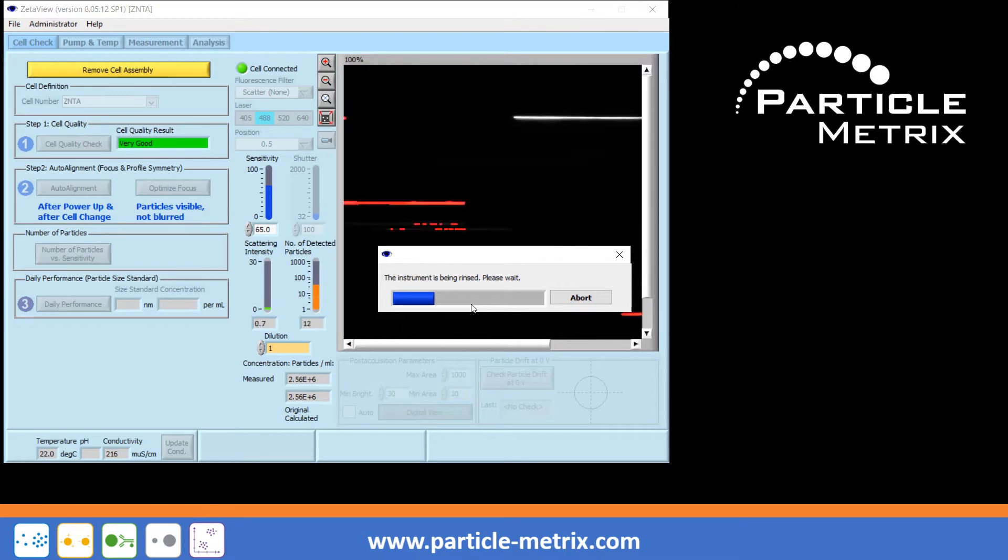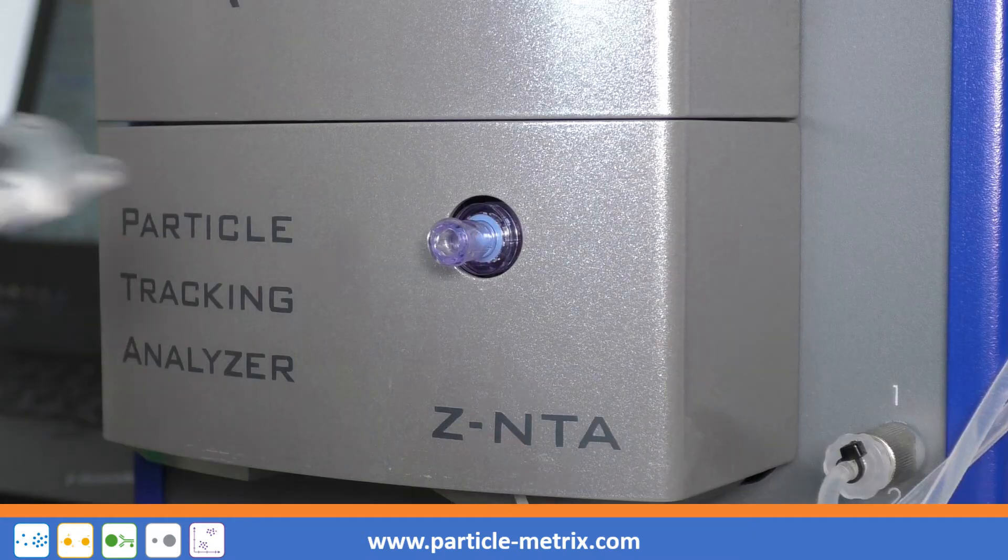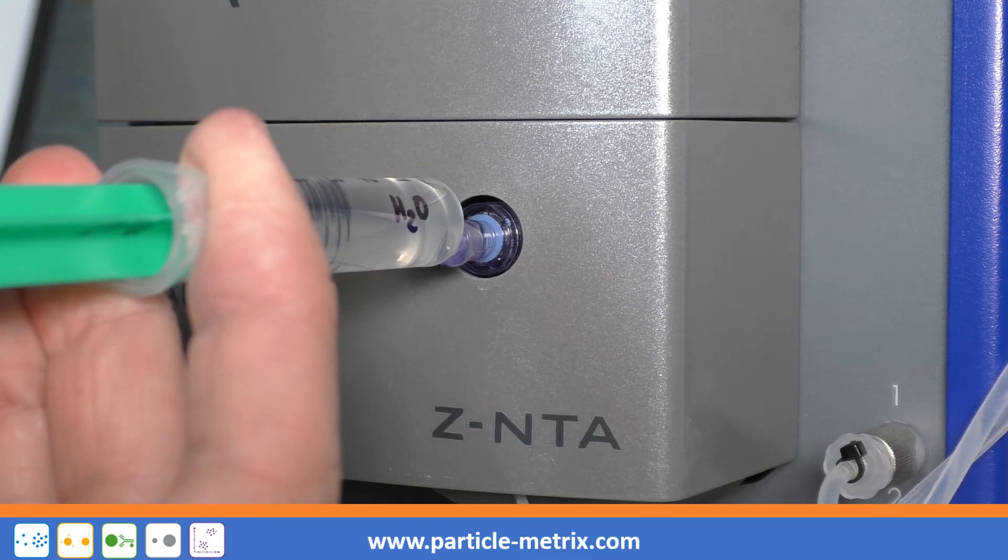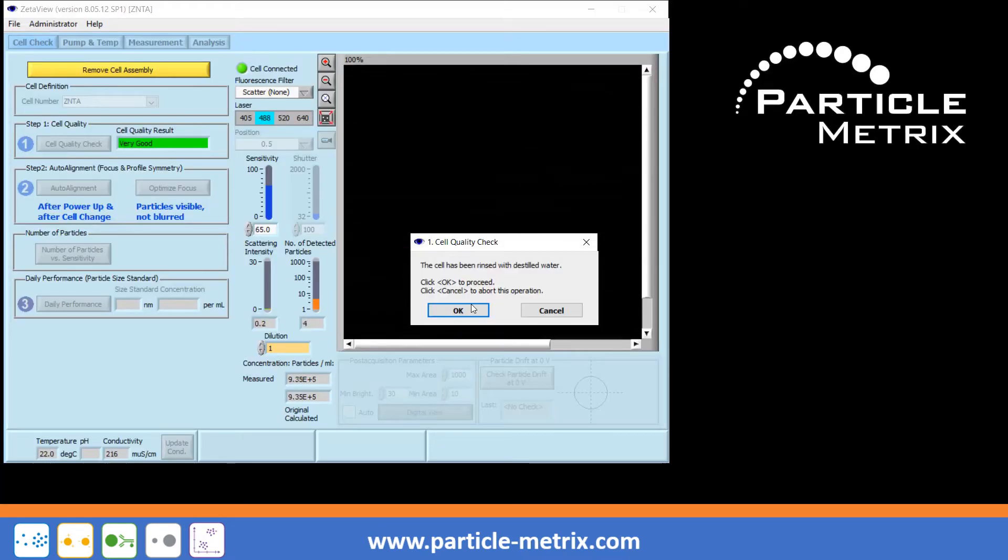While rinsing, it is recommended to inject 10-20 ml of water into the injection port. This is important because the dead volume between injection port and measuring cell should also be filled with water in order to avoid air bubbles.